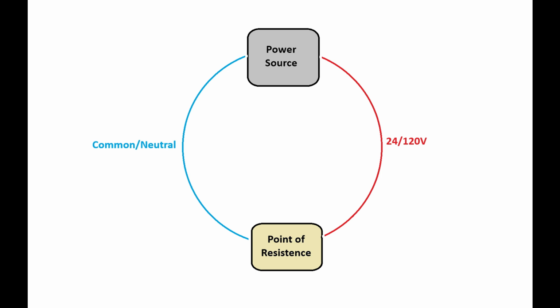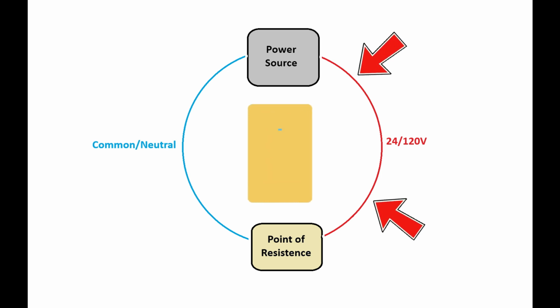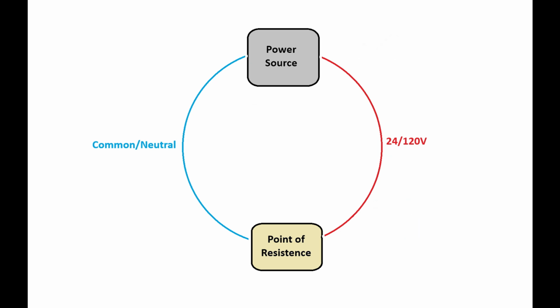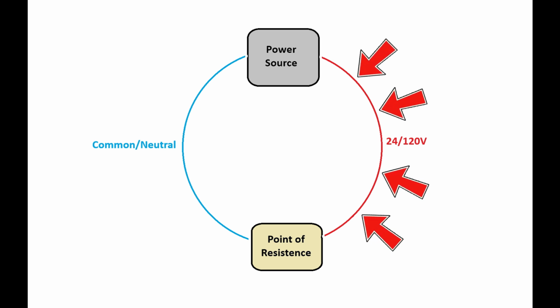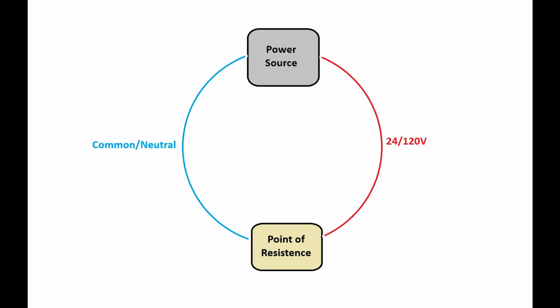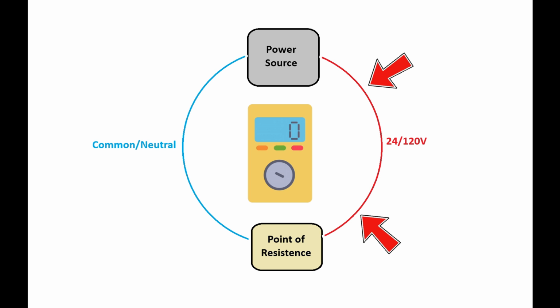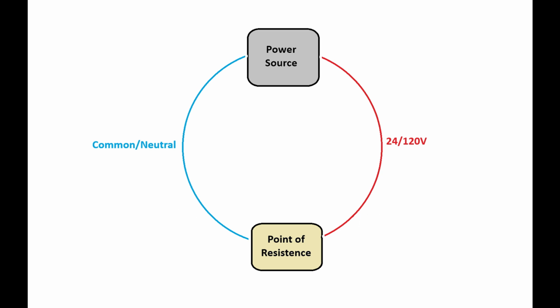If we were to place our probes on the same side of the circuit on either side of that point of resistance, we're going to read 0 volts, whether there's voltage there or not. And this is because there is no potential difference on a wire that's reading 24 volts, 120 volts, or 0 volts all the way through it. The readings are exactly the same all the way through, so there's never going to be a difference. The difference will always be 0. If you're using improper reference points and you're reading 0 volts when there's actually voltage there, or if you're using proper reference points and reading 0 volts because you have a problem with your power source, these are two completely different things. So understanding reference points tells you what you're actually looking at there with your multimeter and points you in the direction of the actual problem.